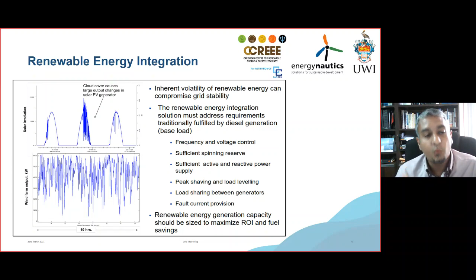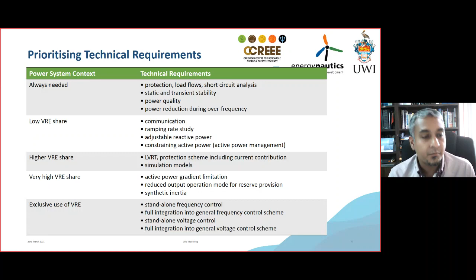Our penetration, from a small share of RE to exclusive use of RE, requires different levels of system studies. What is always needed is a measure of your protection, your load flows, your short circuit analysis. You should be looking at your transient stability, and that only becomes more critical as you increase your renewable energy penetration. I cannot underscore how important it is to have a very firm appreciation, particularly when you are bringing batteries onto the system, of the role that the batteries will play, the need for voltage ride-through capabilities, the need for frequency ride-through capabilities, and how batteries can actually help improve your performance.